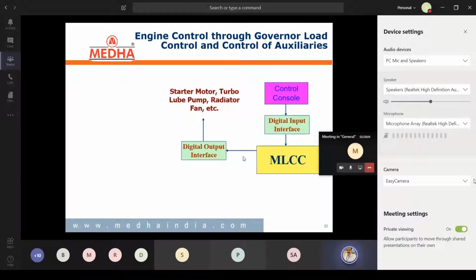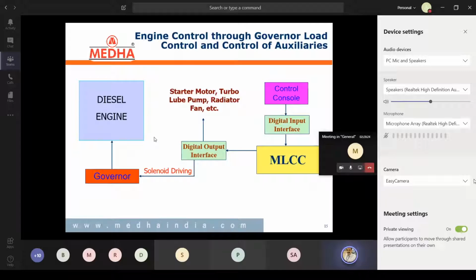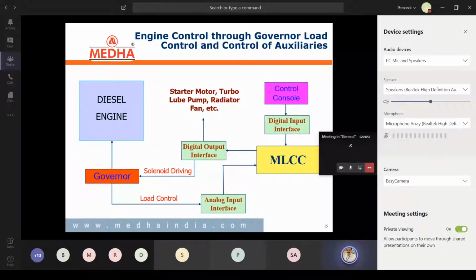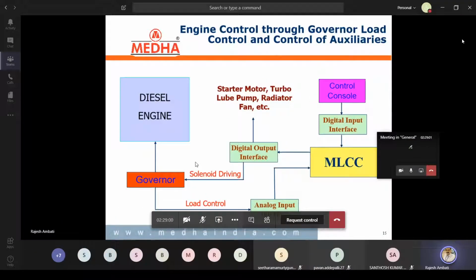Then based on this, the system drives outputs to generate signals for different starter motors, turbo lube pumps, radiator fans, and solenoid signals for the governor. Okay, low side drive, high side drive, whatever it is. All these are low side drive outputs, and ultimately the governor controls the fuel rack so that engine RPM will be maintained constant. And from the governor, the signal will be monitored by the control system, that is LR, load regulator. Like Alco locomotive LCP, similarly here LR value, but as per this design here it is a 0 to 72 volt signal. In Alco it is maintained between 24.4 and 68.8 volts LCP, but here it is LR, load regulator voltage. And in the display, one more difference is that in Alco LCP percentage should be 0, but in HHP LR percent should be 100% for normal operation.